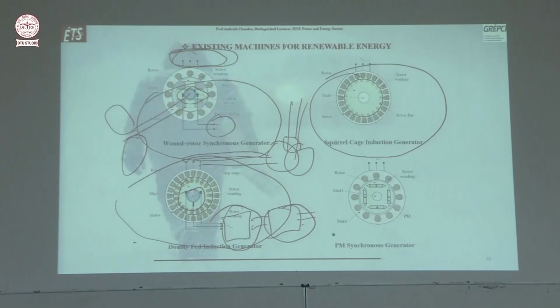So like Hydro-Quebec started with 1.5 megawatt size doubly fed induction, because in Quebec, the Hydro-Quebec is using doubly fed induction generator for all the wind farm to generate 4,000 megawatt of wind energy. Initially, they started in 2007 with 1.5 megawatt machines with 500 kilowatt, 2 back-to-back converters. But then with the development of technology, the DFIG machine, they started using 2.6 megawatt, and now they are using 3.6 megawatt of doubly fed induction generator in the system.